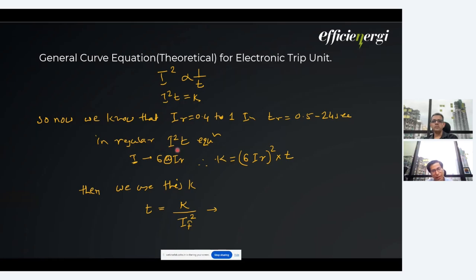Then in regular I squared T, first of all, we have to obtain this K. To obtain this K, we need to know what is the I that we should be considering and what is the T that is there in the set value. So normally what we do is take 6 times the IR as the base for I. Let's say we have considered 1 as IR, 1 into IN. Then that will be 6 into 1, that will be 6 squared, and for time, let's say we have considered 3 seconds as the tripping time. What does this basically mean? It means that when the current goes to 6 times the set current, then the particular breaker will trip on the TR. If we have set it as 3 seconds, then it will trip in 3 seconds.